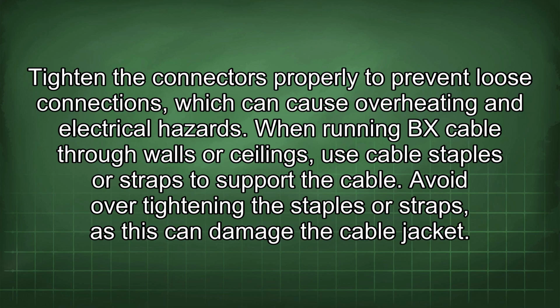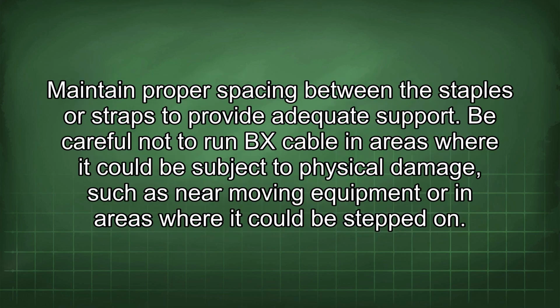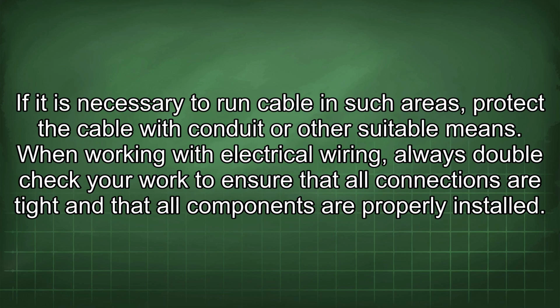When running BX cable through walls or ceilings, use cable staples or straps to support the cable. Avoid over-tightening the staples or straps, as this can damage the cable jacket. Maintain proper spacing between the staples or straps to provide adequate support. Be careful not to run BX cable in areas where it could be subject to physical damage, such as near moving equipment or in areas where it could be stepped on. If it is necessary to run cable in such areas, protect the cable with conduit or other suitable means.